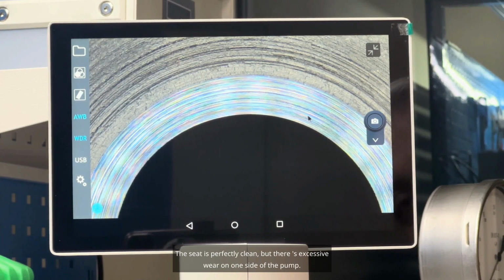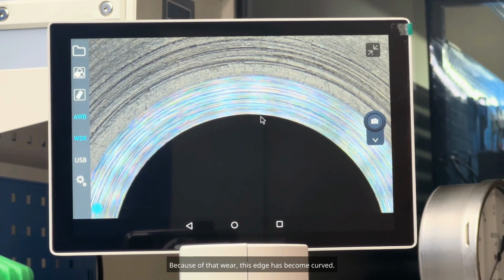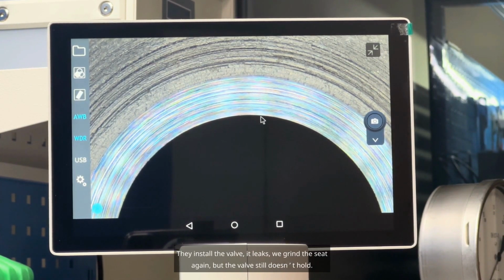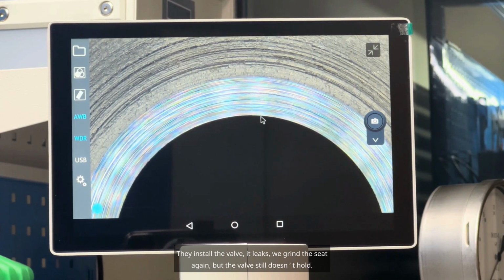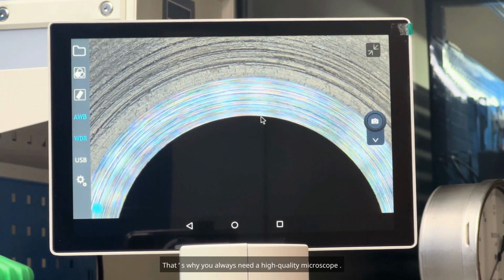The seat is perfectly clean, but there's excessive wear on one side of the pump. Because of that wear, this edge has become curved. They install the valve, it leaks. We grind the seat again, but the valve still doesn't hold. That's why you always need a high-quality microscope to inspect the pump seat.